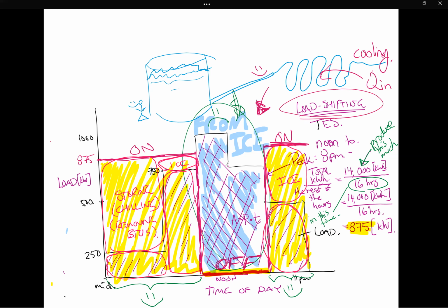That's called load shifting. The fact that you now have an 875 kilowatt compressor, smaller than the 1,000 kilowatt compressor you used to have, but you're also turning it on and off again - because you're turning it off, it saves lots and lots of money. So this is an excellent energy savings opportunity for peak load shifting.